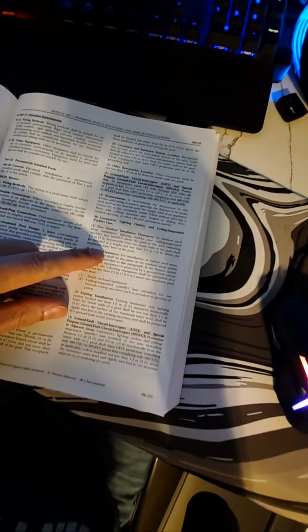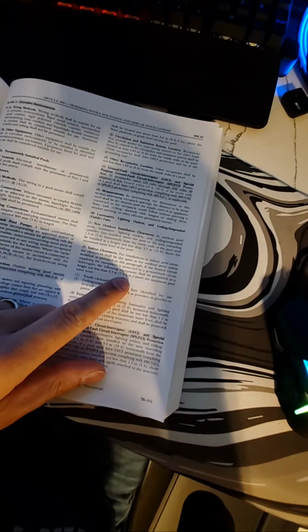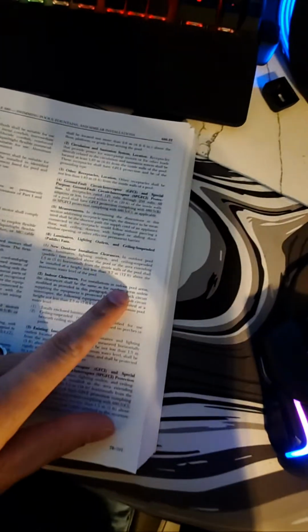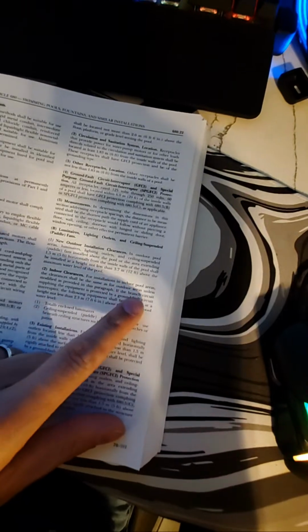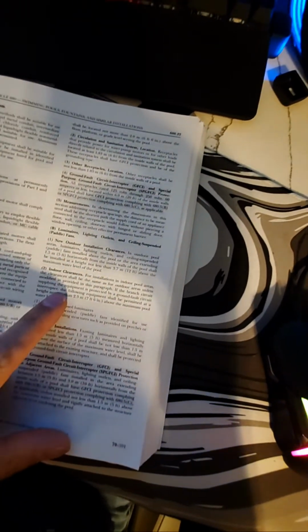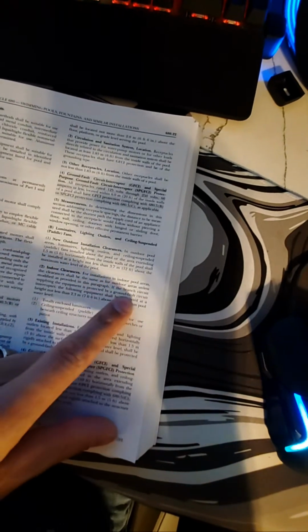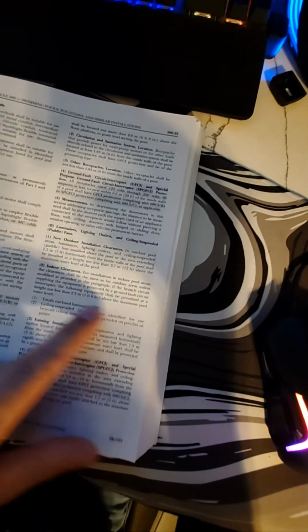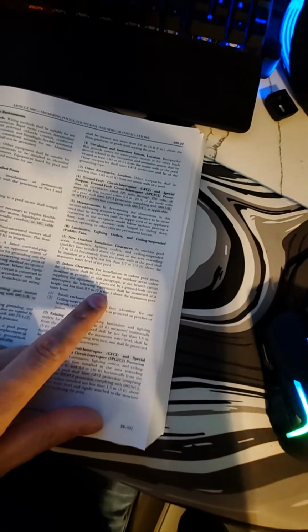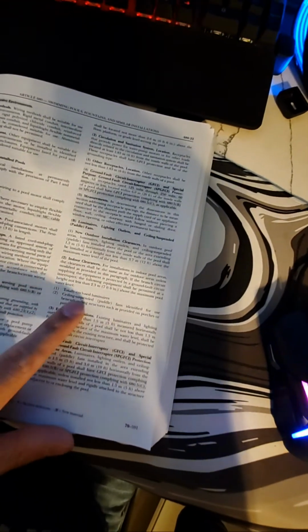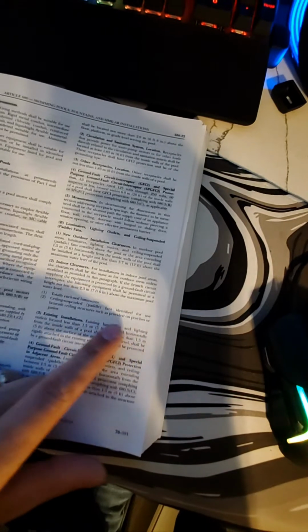Here's your indoor clearances. Okay. Here's 6 foot 7 inches. Let's see what it says. Installations, indoor pool areas, same as outdoor areas unless modified. Paragraph, the branch circuit supplying the equipment is protected by ground fault. The following equipment shall be permitted at a height not less than 7 foot 6 inches.